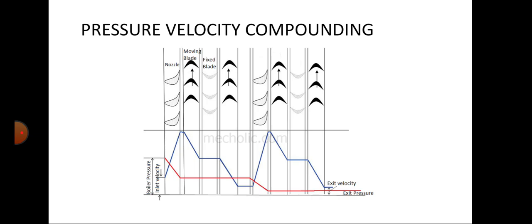Looking at the velocity graph: once the steam enters the nozzle, the velocity gets increased, and then it gets decreased as the kinetic energy gets consumed in the moving blade. After consuming, the steam enters the fixed blade or guide blade. The guide blade guides the steam to the moving blade with no change in velocity or pressure. Then it goes to the moving blade where the velocity decreases further, reaching the bottom point at the end of the stage. The pressure also decreases. Moving on to the second stage, as the velocity is at its bottom, it needs to be increased to further gain kinetic energy, so another set of nozzles is given where the velocity gets increased to its peak, and the increased velocity is utilized by the further moving blades.